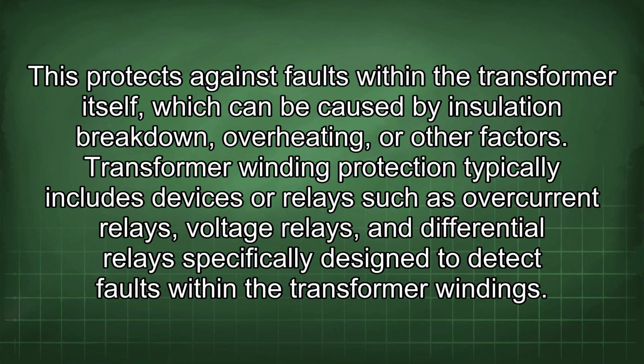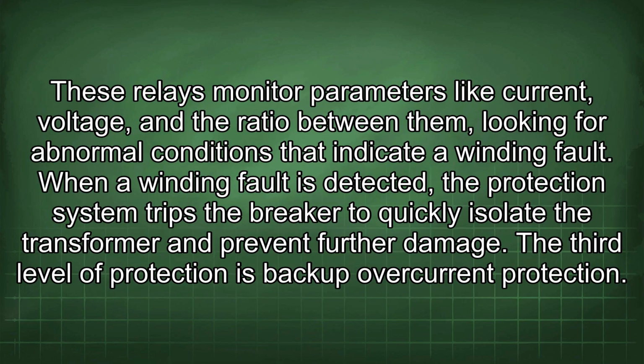Transformer winding protection typically includes devices or relays such as overcurrent relays, voltage relays, and differential relays specifically designed to detect faults within the transformer windings. These relays monitor parameters like current, voltage, and the ratio between them, looking for abnormal conditions that indicate a winding fault. When a winding fault is detected, the protection system trips the breaker to quickly isolate the transformer and prevent further damage. The third level of protection is backup overcurrent protection.